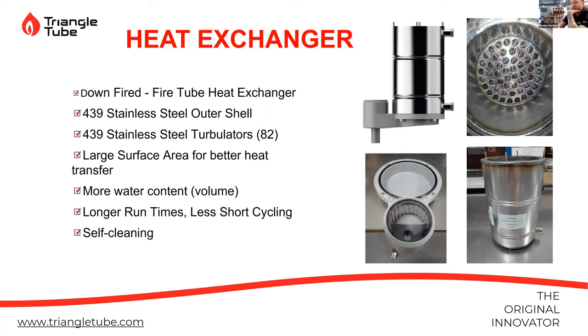So we've got a down-fired tube heat exchanger on this boiler. Something you'll see in the sales marketing and the sales guide is self-cleaning. With the burners being fired down, we have that condensation building up in our tubes and going down through our heat exchanger, and the condensation will pull a lot of that debris in and out. But around this heat exchanger, you can still have sediment and debris build up in here.